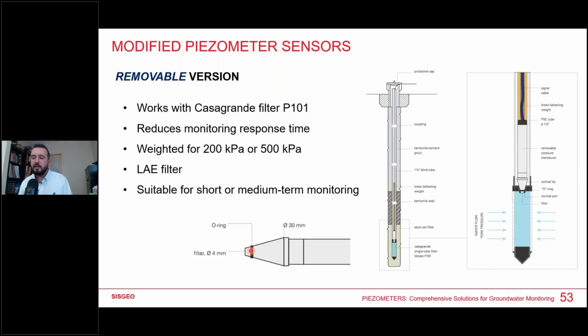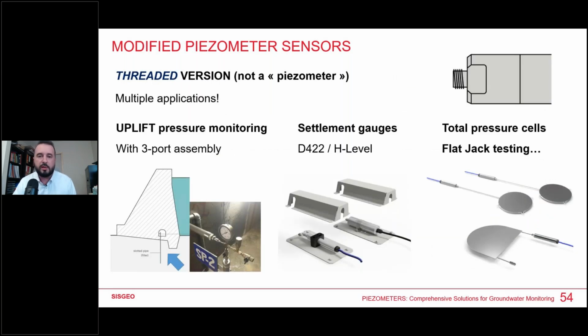So the advantage of that is that it's removable. Like the name indicates, you can retrieve it and then put it in another borehole. And the principle is that it reduces the volume of the chamber. So instead of waiting for the water to rise and stabilize here, the volume is quite small, so it reacts quickly.